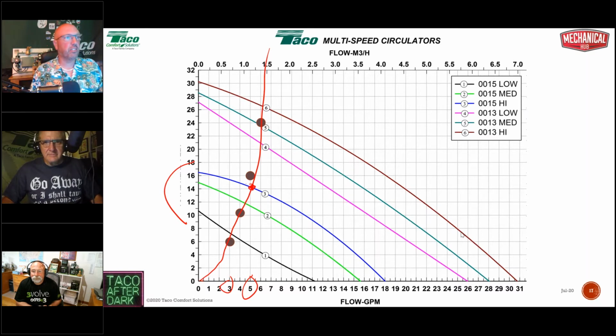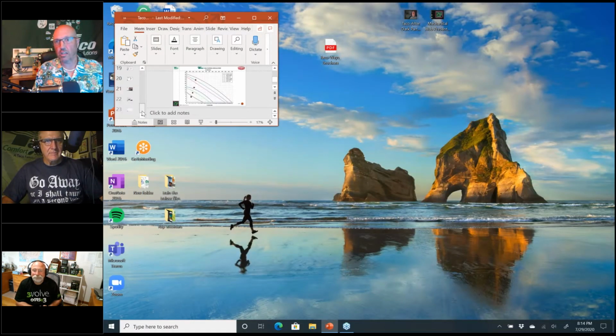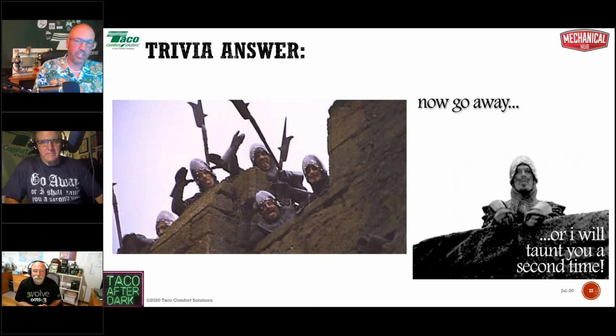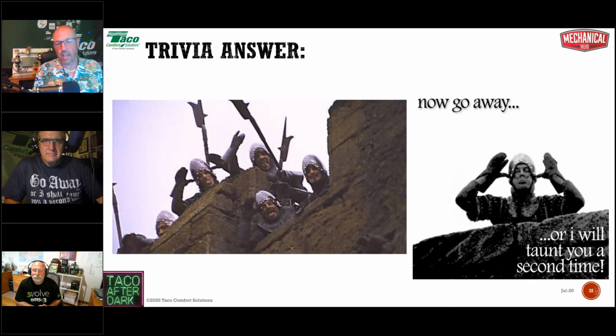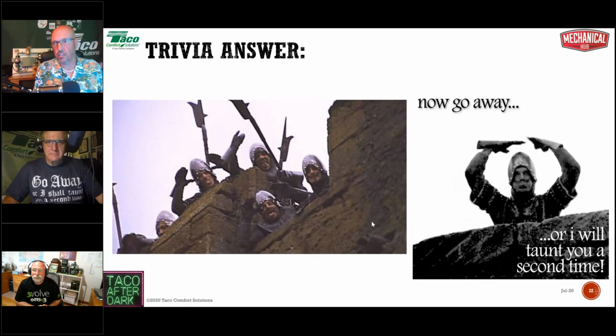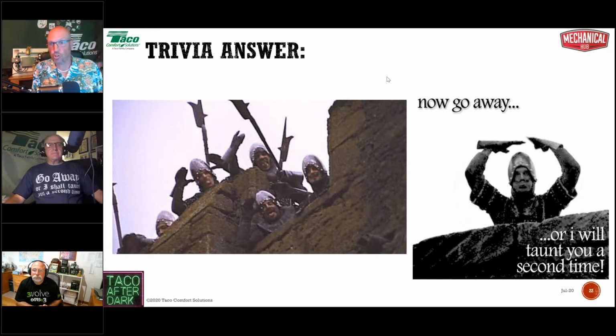Question right before from Gerald, he's saying it might be a crazy question, but if you have a simple modulating boiler, is there an ECM circ which has external sensors which could max the delta T of the circulator? So, right now I would say no. There are boiler manufacturers out there, Rick was talking about earlier today, that can deliver a 0 to 10 volt signal to a circulator to tell it what speed to run at, so it gets the desired delta T. We have them, we call those our 00 VV circulators, variable voltage. They are available as a straight AC circulator, not an ECM circulator. Some of our larger circs are starting to come with the 0 to 10 inputs. We don't have it on the small side just yet. So excellent question, Gerald, there.